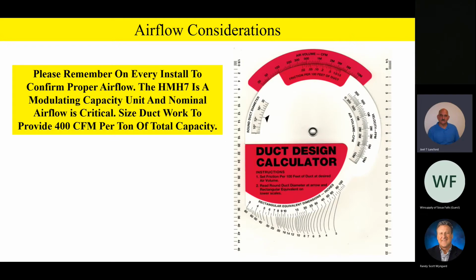Let's talk a little bit about airflow considerations, because remember, on every install, you want to confirm proper airflow, especially on a modulating system. So the HMH7 is a modulating unit. It's going to modulate between 35 and 100% capacity, and nominal airflow is going to be critical. Now, this has to go with anything that's modulating, because any modulating unit is going to be looking at the refrigeration circuit and determining at what point of modulation or capacity reduction it's going to need. So ductwork sizing is very, very important.